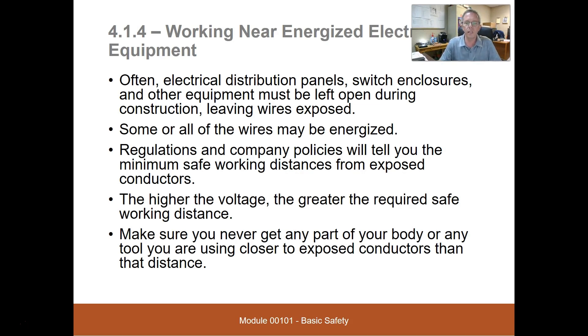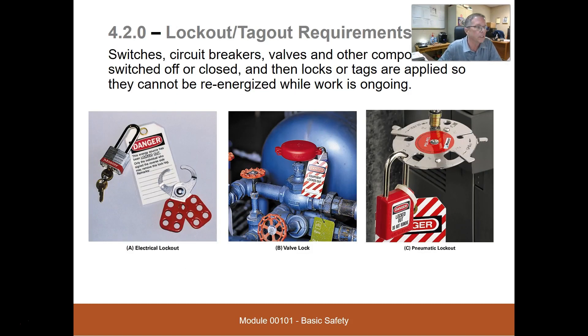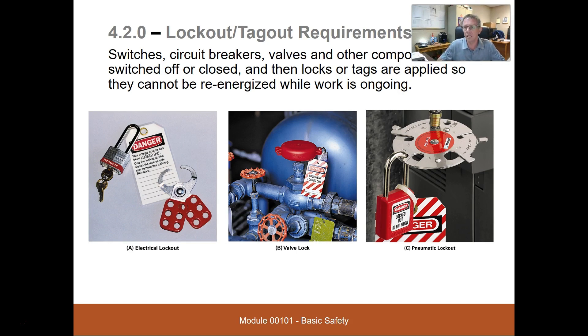When we talk about lockout/tagout, our electrical and industrial maintenance students tend to think only of panels and disconnects, but lockout/tagout must cover anything in that area that could release any stored energy and hurt you in any way. When I go in there, I have to look at everything in the area and find a way to lock, tag, or block anything that may release any form of stored energy.